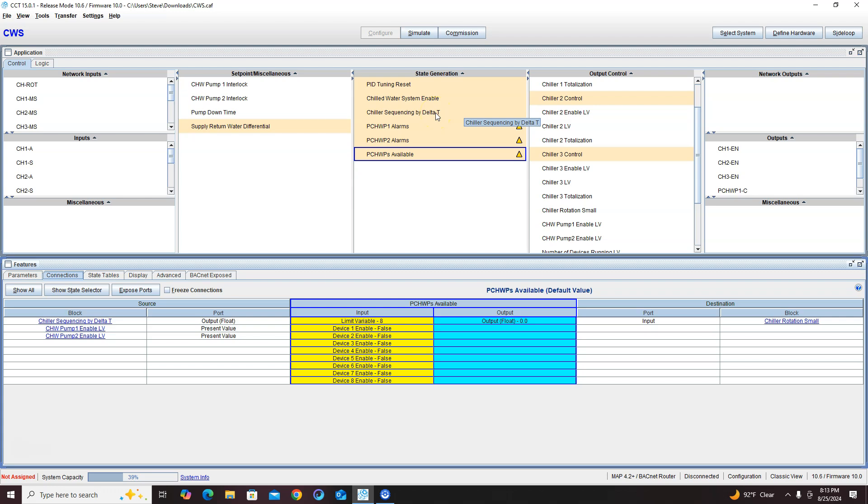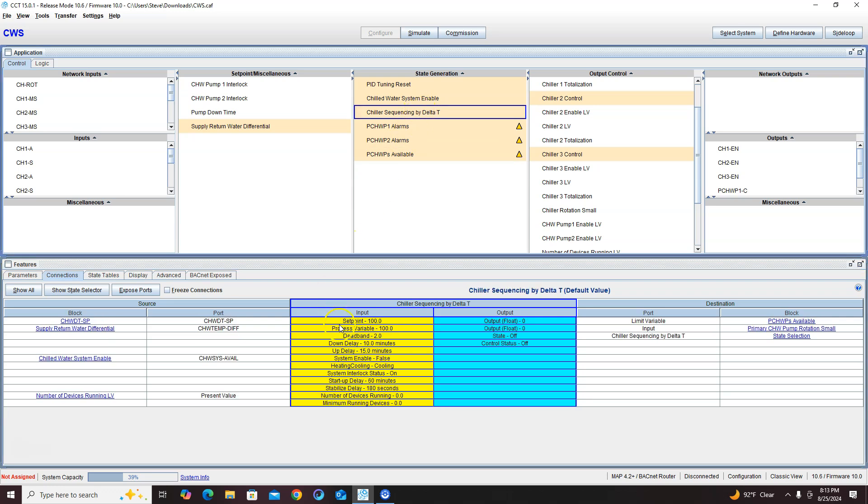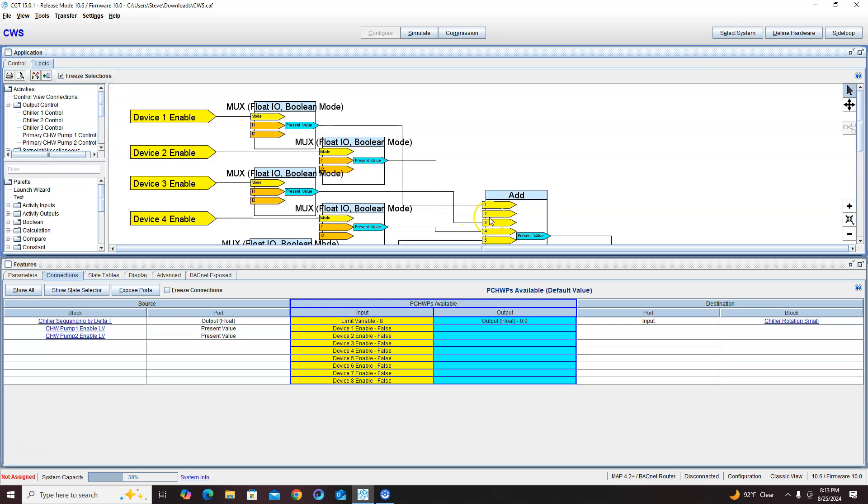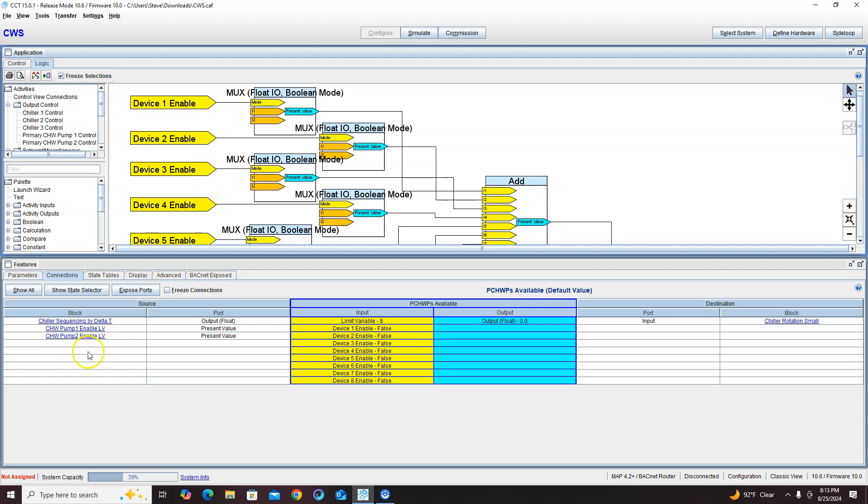That's going to sequence it up. So this sequence will keep rising one, two, three, four, five - it doesn't know how many chillers you have. The number of devices running, so it will add to the number of devices running, so it'll actually get up to three if you have two devices running over here, but chill water pumps will never let three go out here. And let me show you that - view the logic.